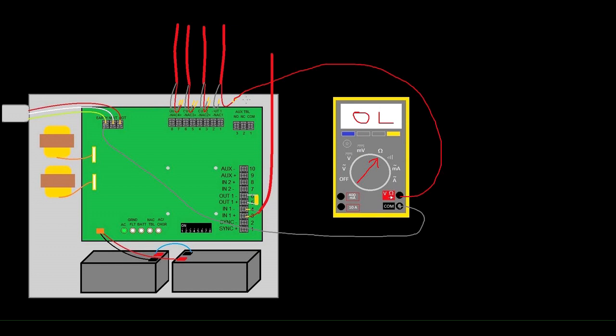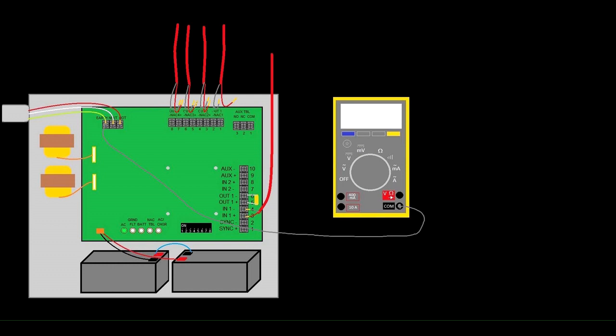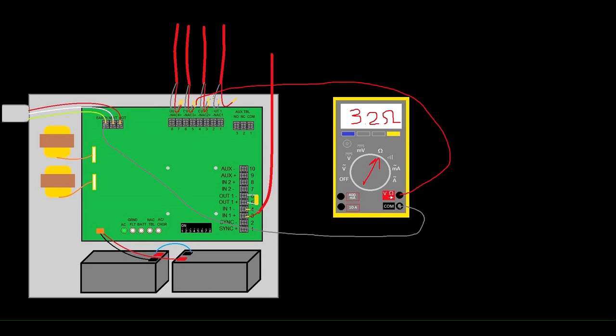All right, we're going to assume that you went through this first red wire, it was open, you went to the gray or black wire, that was open, and then the same thing on the next two. Let's just make up a scenario. Let's say that when we metered these two wires that's when we got our ground fault, and I circled NAC3. So let's say on NAC3 on the red we got 3.2 ohms. Now there's a good chance something weird would happen, or at least something that might seem weird when you take your meter off and you go to the other wire, and that is what I would expect to get would be 4.7 k ohm or somewhere in that range.